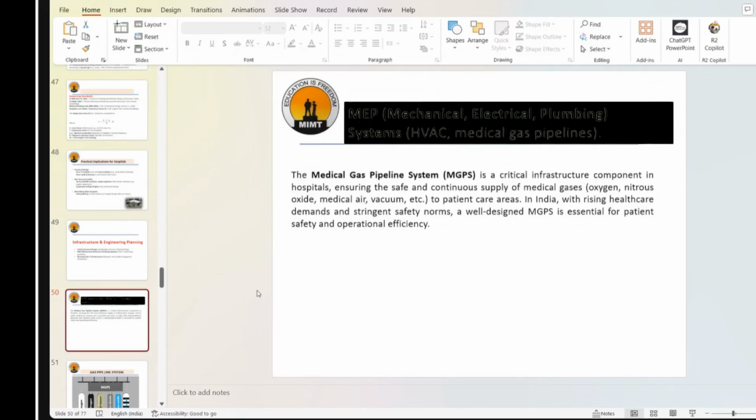So that's why this pipeline system is superior to the conventional system. एंड बेसिकली जो इसमें गैस लाइंस होती हैं, ऑक्सीजन है, नाइट्रस ऑक्साइड है, मेडिकल एयर है और वैक्यूम, इनकी हमें जरूरत होती है. वैक्यूम, ऑक्सीजन, ये मोस्ट कॉमन हैं. नाइट्रस ऑक्साइड we are using for anesthesia purposes, but vacuum, सक्शन में we need some kind of vacuum, तो सक्शन में it is useful. And oxygen is, as you know, important in case of any person who is facing low oxygen saturation in the blood.